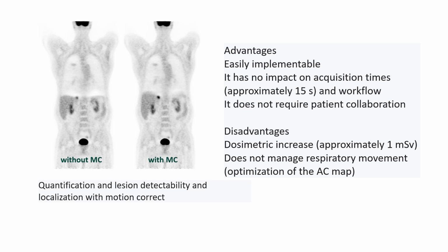The last described technique has some advantages. First of all, it is easily implementable. It has no impact on acquisition time, with approximately only 15 seconds added, and on the workflow. It does not require patient collaboration, but it has the disadvantage that it is associated with an increase in dosimetry for the patient, approximately 1 millisievert for the CT component.